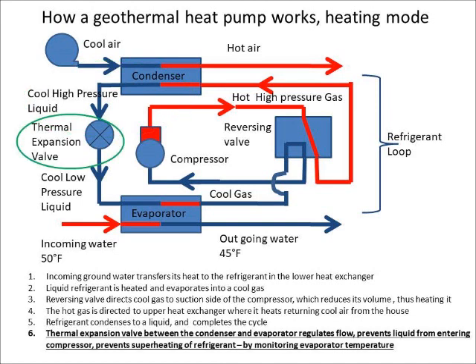Sixth, the thermal expansion valve allows the cool, high-pressure liquid from the condenser to expand to a cool, low-pressure liquid into the evaporator. It prevents liquid from entering the compressor and prevents superheating of the refrigerant by monitoring the evaporator temperature.